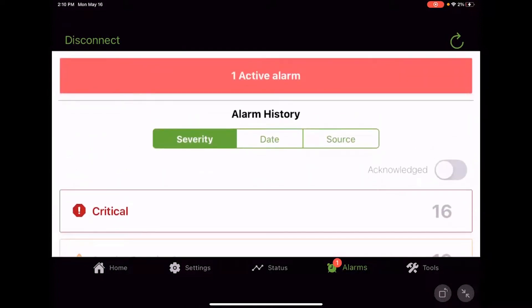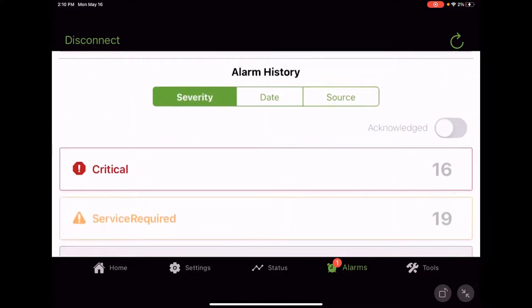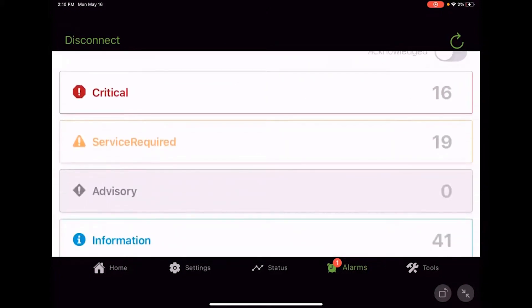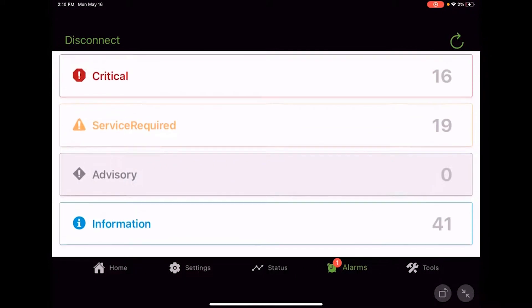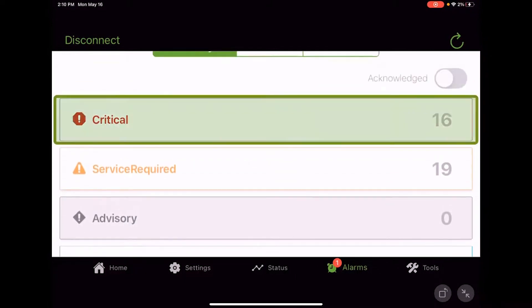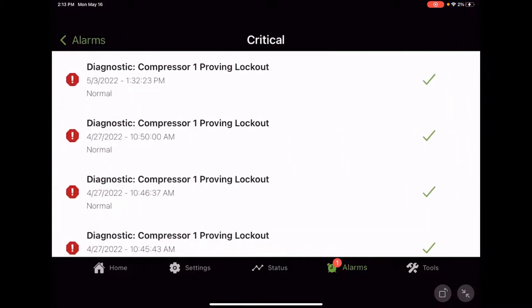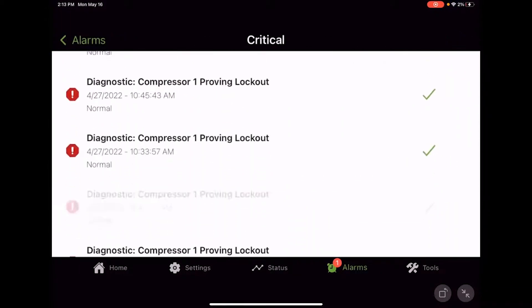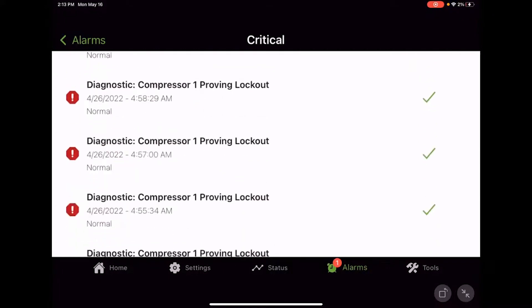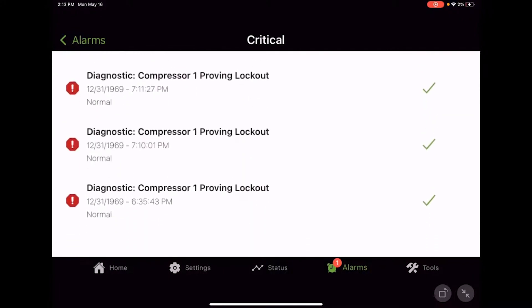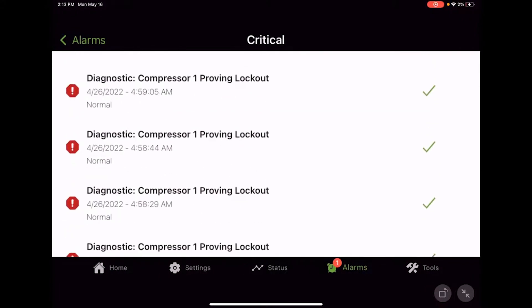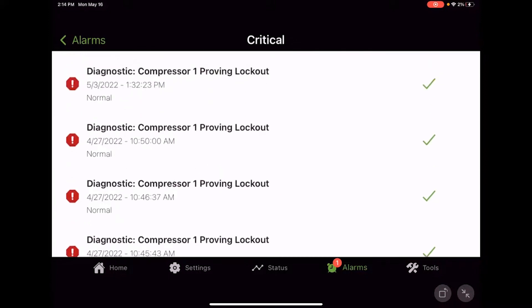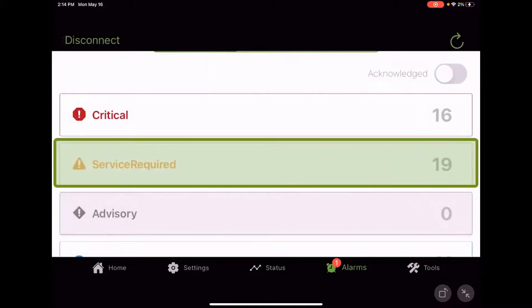So we can sort by a couple different things. We've got severity, so how important is this alarm? And we've got four categories here. We've got the red stop sign with the exclamation point. That's critical. That's like pretty important stuff. Generally going to be things that lock out the unit or lock out a circuit. Of course, looks like we've had a lot of fun with that compressor one proving circuit. So there's your critical.